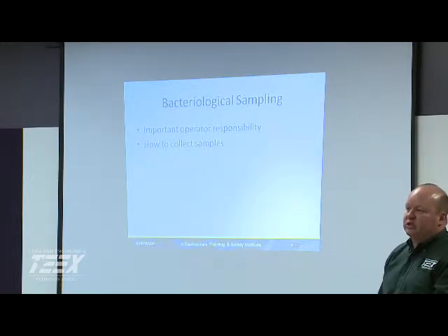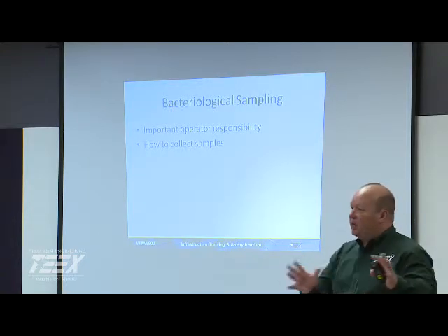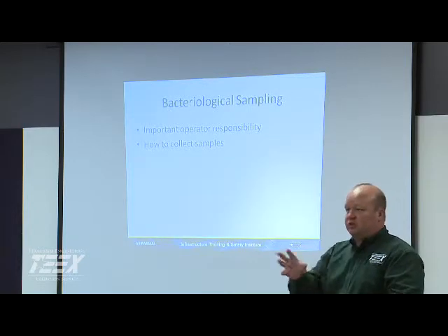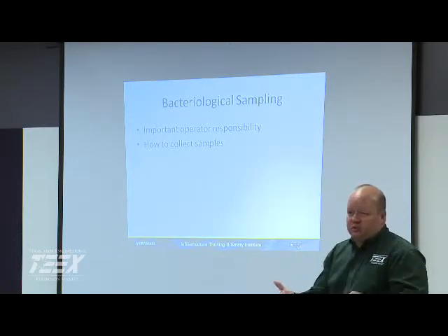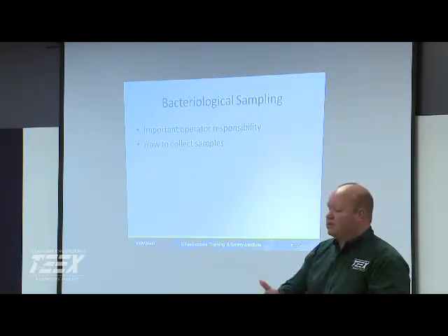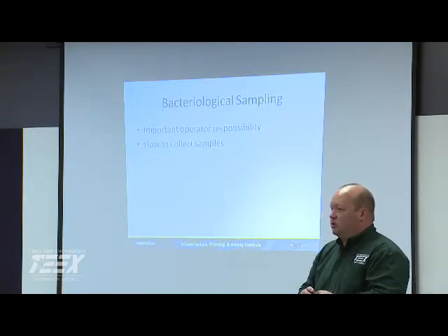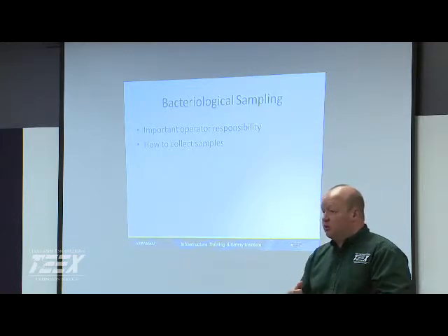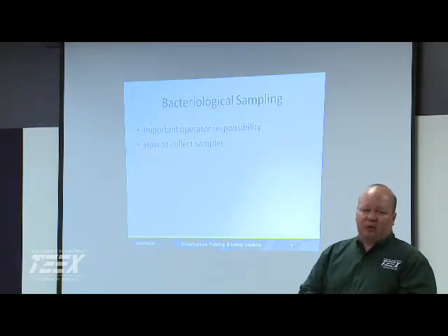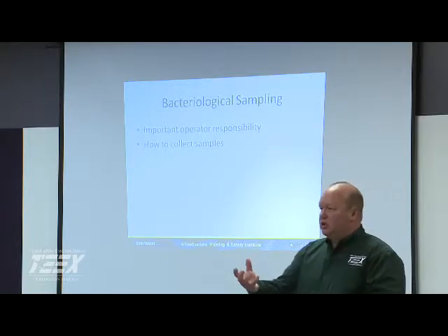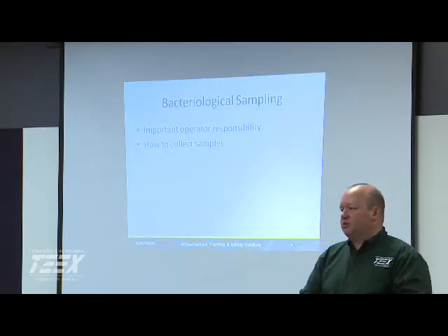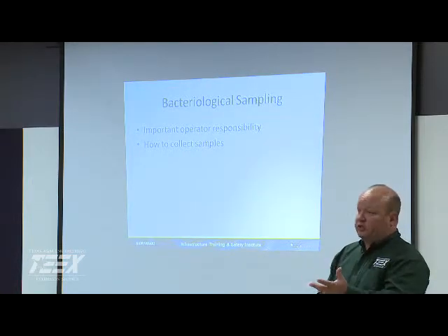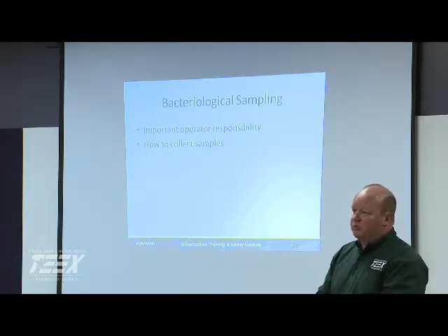We had a question yesterday about wearing gloves. I would highly recommend against wearing gloves. Make sure you disinfect your hands well. We're going to get into it on the system, but make sure you disinfect. What do you do for disinfection on your tap? They asked about Lysol. I personally wouldn't like Lysol to be used. I prefer a bleach solution in a spray bottle. Most people aren't flaming anymore. There are plastic components and rubber seats that are going to melt. But a good proper disinfection and a good flushing time are all really important for them to have a good understanding of.